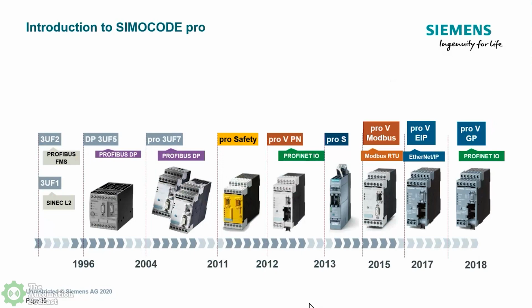And then in 2018 we came out with a little more cost-effective unit that only measures current, and it has the ability to expand one card, meaning I can expand a digital module or, pardon me, an analog module, but that's it, one card. With the full-blown version, the PROFINET Pro V, you can expand 2 digital cards, 2 analog cards, 2 temperature cards, up to 7 modules. Wow. And be able to expand. But with the GP, to make it a little more cost effective, it's only able to expand 1 module.